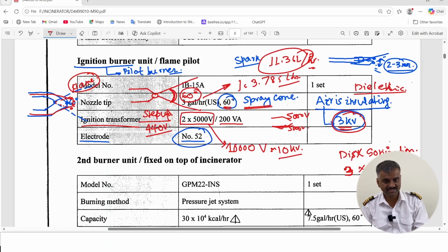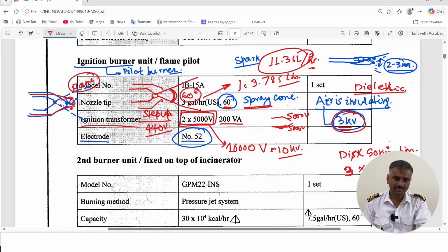First thing is this, and second is the potential. Why do you need 10 kV of potential to create a spark when only 3 kV is sufficient, and what is the dielectric strength of air? That you need to overcome. This is the concept behind the ignition burner and the pilot burner. A very detailed video will also come in this section, where we will discuss what happens if you alter the position of the electrode tips or the position of the nozzle. That will be covered separately.